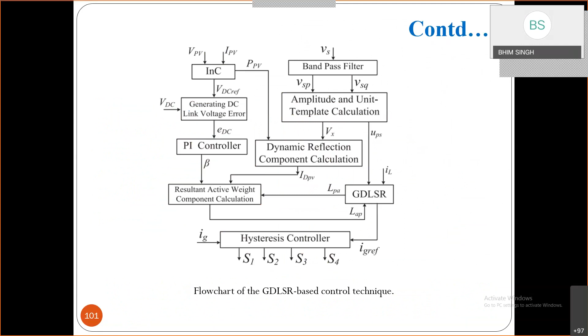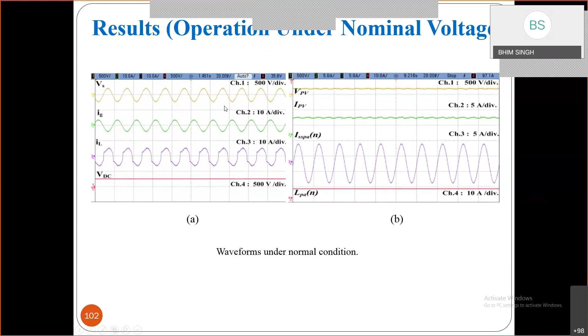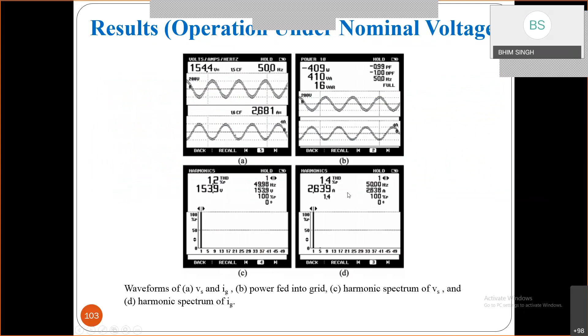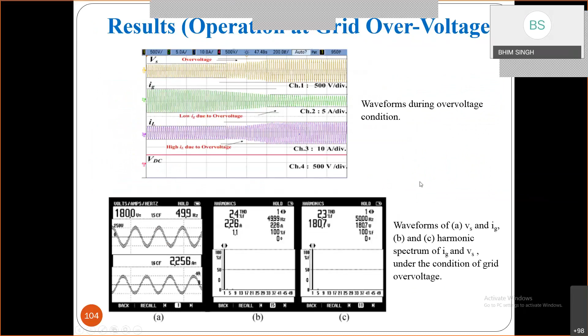You can clearly see the grid voltage and grid current are in phase, meaning power is going to the grid, and it is also compensating the load locally. It's a nonlinear load compensated by the same inverter, making the current sinusoidal at unity power factor on the grid side. We are able to get a THD of the grid current of 1.4%, even with a voltage THD of 1.2%. Even when you have over voltage or under voltage, the system works very well, and you can see the grid current THD is still quite low.